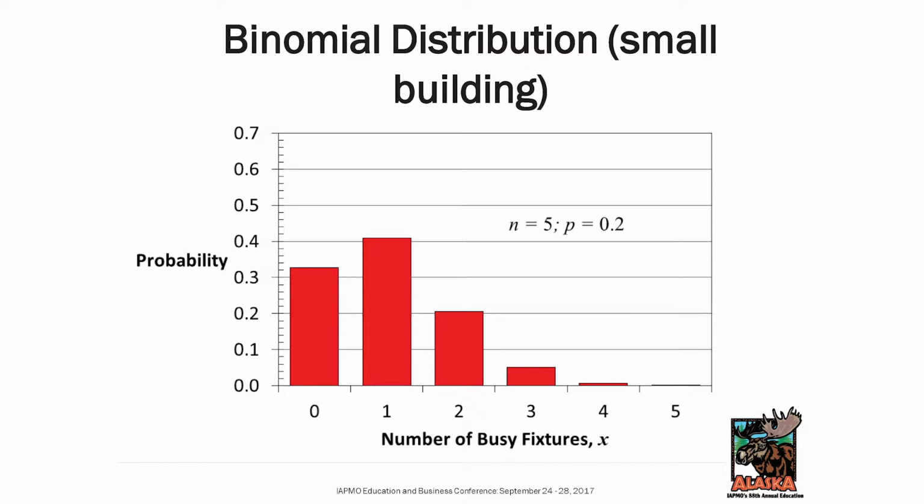Here's the problem child. In single-family dwellings there is not a high frequency of flow, so you have a high probability of stagnation, of no flow. And this drives the mean flow rate down, and that's why we're getting such low outcomes using the Wistort method. You don't design a building for no flow. You design a building for flow, and pipe sizing for flow.